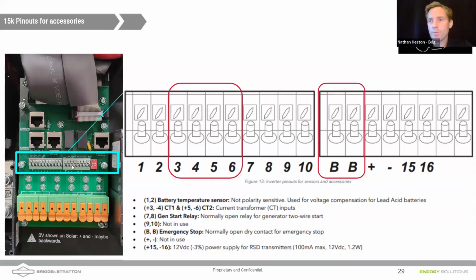Daniel, what is a CT? A device that can measure current flowing through a wire, I believe by the magnetic field it generates, without actually having to touch the wire. Again, yeah, amps, so not volts. Exactly. So a CT is a current transformer, and it does exactly what Daniel's saying. It essentially looks at the induction that's happening through that wire in a number of coils, and those coils provide an output voltage, and that output voltage can signal how much AC current is passing through the CT. Those get wired into 3, 4, 5, and 6.